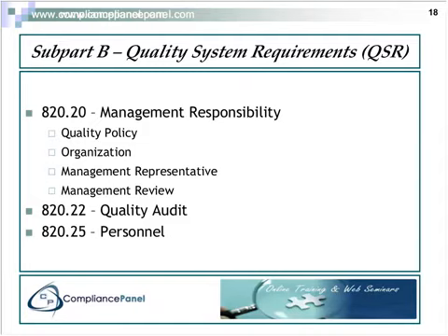820.25 is very important because it explains the necessity for properly trained personnel. And one very important note that's under the clause of 820.25 is that personnel who are responsible for releasing the product, in other words, the people who are saying this product is good or this device is good for use in a clinical environment, they must be made aware of the defects and errors that could occur. So as part of training within your organization, the people who release the product need to know that if this product doesn't work correctly, what can happen, what are the adverse events that would be associated with this.